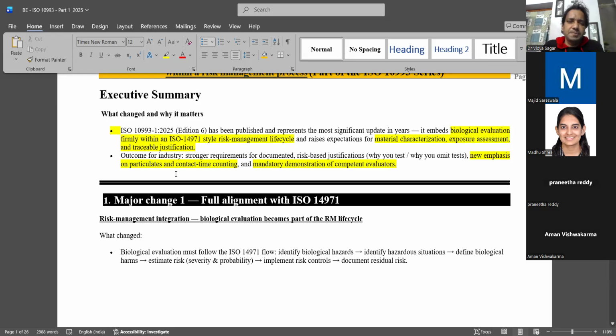Okay, there is emphasis on particulate matter. We never discussed particulate matter for a lot of devices. Now, for every device, you need to explain what the particulate matter is. It's not only the number, but also the size of the particulate matter. For any device in contact with the human body, you need to add one more specification in your technical specification sheet or in your COA, that the total particulate matter is so much on the device and what the size of it is.